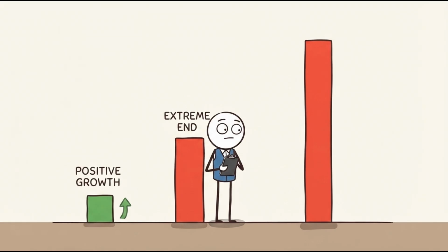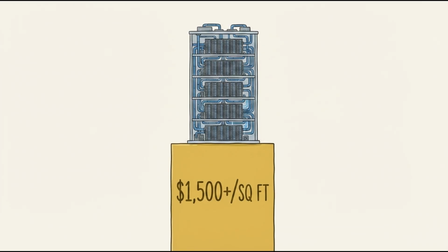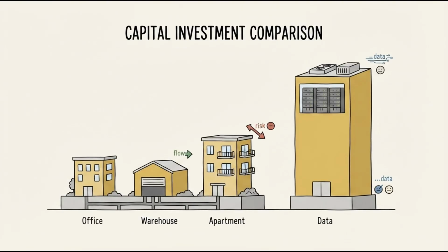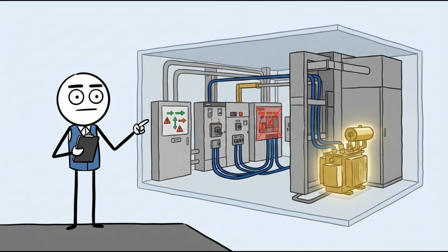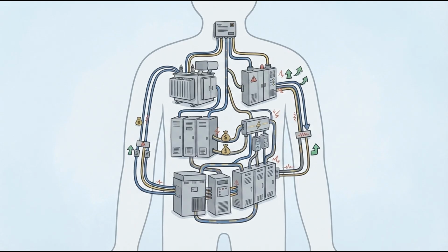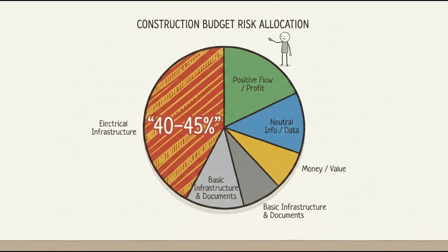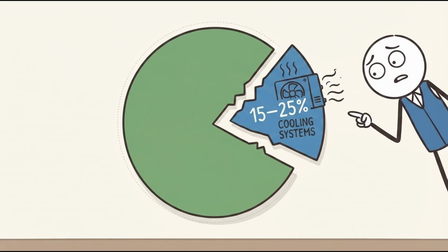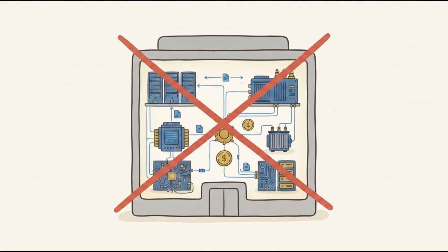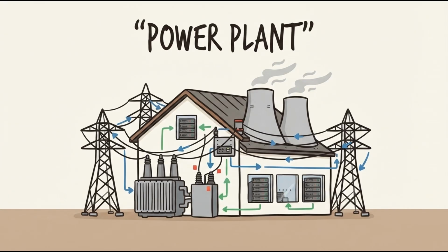And at the extreme end, fully AI-optimized builds can exceed $1,500 per square foot, several multiples above almost any other commercial property type. Electrical infrastructure alone, the switchgear, the transformers, the uninterruptible power supplies, consumes 40 to 45% of the entire construction budget. And cooling systems eat another 15 to 25% on top of that. This is not a building in any traditional sense. It is closer to a purpose-built power plant that happens to have a roof over it.